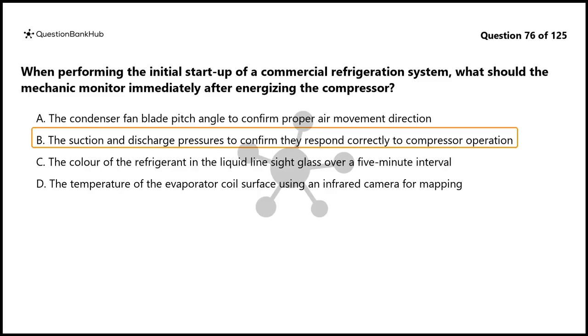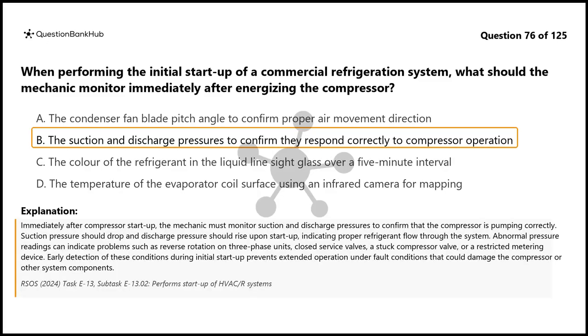The correct answer is B. Immediately after compressor startup, the mechanic must monitor suction and discharge pressures to confirm that the compressor is pumping correctly. Suction pressure should drop and discharge pressure should rise upon startup, indicating proper refrigerant flow through the system. Abnormal pressure readings can indicate problems such as reverse rotation on three-phase units, closed service valves, a stuck compressor valve, or a restricted metering device. Early detection of these conditions during initial startup prevents extended operation under fault conditions that could damage the compressor or other system components.